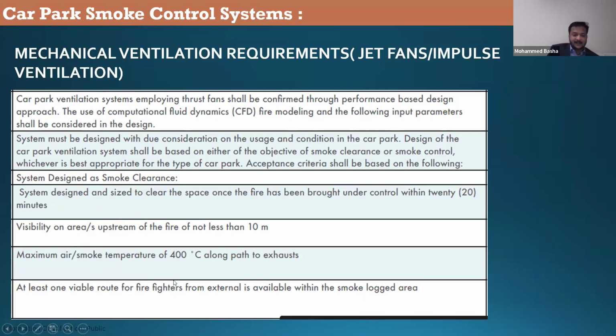Because why they're telling firefighters 400 degrees, you can understand from here. Civil Defense allows you to have this kind of system also. You do not need to have a smoke exhaust system running during the fire mode. You can design for a smoke clearance system, but they will ask you one thing: if you want to use a smoke clearance system, prove that the smoke will not come down before the occupants are evacuated from the fire zone.